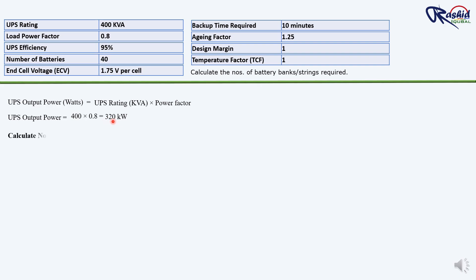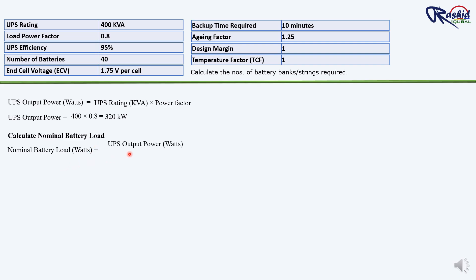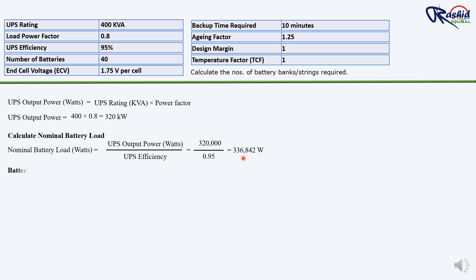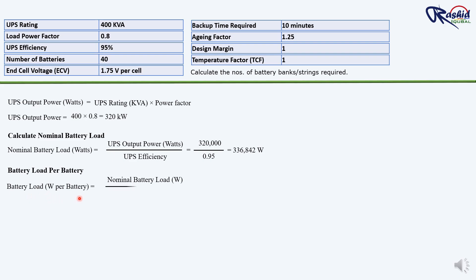Next, we calculate the nominal battery load: nominal battery load = UPS output power ÷ UPS efficiency = 320,000 W ÷ 0.95 = 336,842 W. Then, battery load per battery = nominal battery load ÷ number of batteries = 336,842 ÷ 40 = 8,421 W per battery.